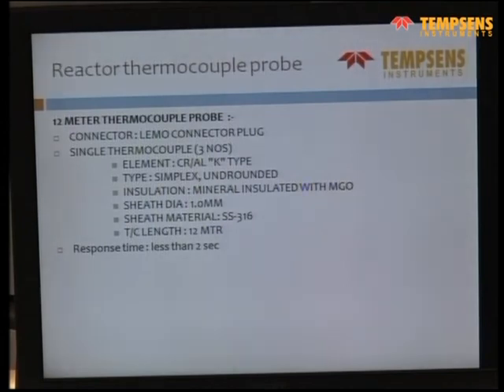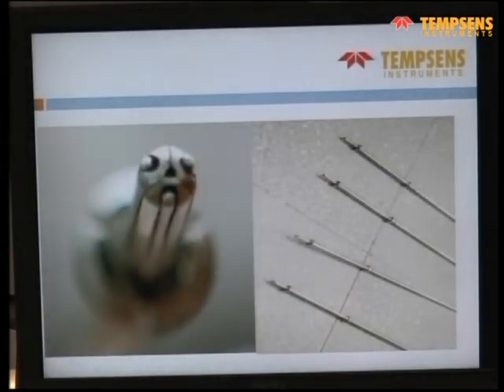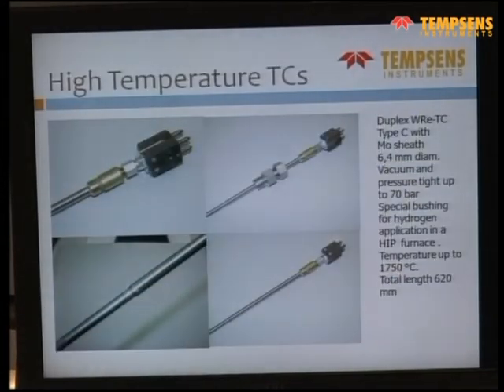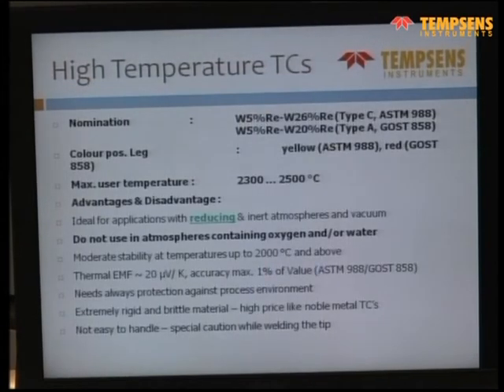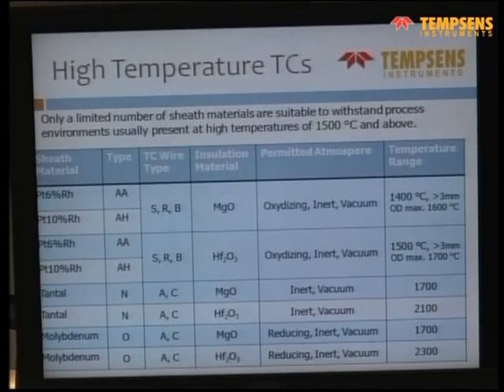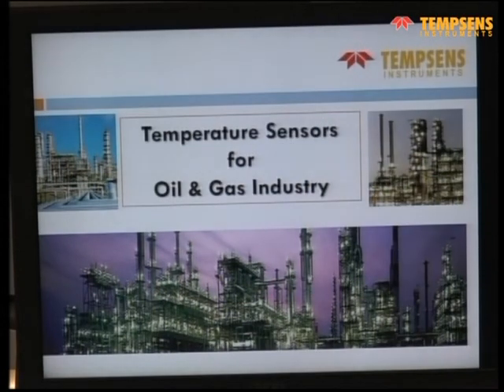So this one is for the reactor thermocouple probe. So these are 3 sensors. This is for IGCAR and fast response time and all those requirements are there. So these are C-type thermocouples, tungsten rhenium for high temperature. We already discussed with Mr. Clem, up to 2300 degrees centigrade with moly or tantalum sheathing, normally C-type can be offered.